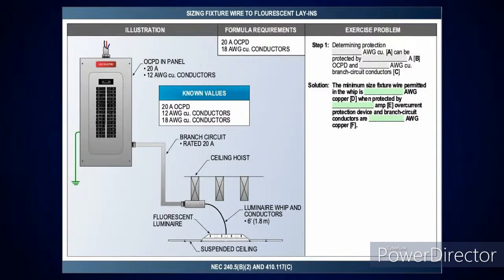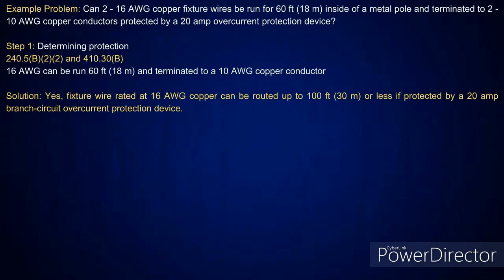Absolutely. And then here's a good example. Like I was saying, you had the luminaire that's there and you're coming over there with a whip. And this same thing here, we've got some known values. Got a 20 amp overcurrent device. You got number 12 conductors and number 18 conductors. Well, where are the number 18s? That's going to be in the luminaire. So when they start looking at the branch circuits, basically going to tell you that that number 18 can go up to what? That 20 amp connect to it. And it's going to be problematic for them to call the inside of that luminaire the outlet when the 18 gauge is actually terminating at the outlet.